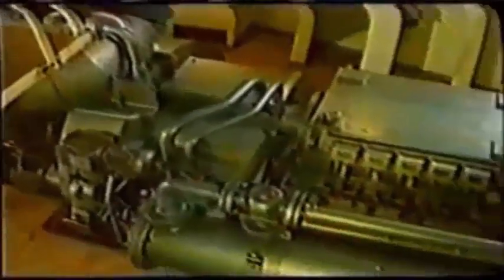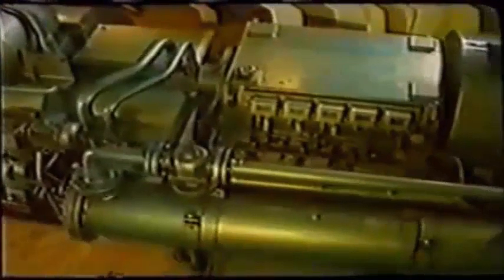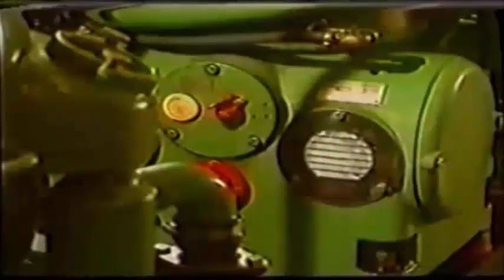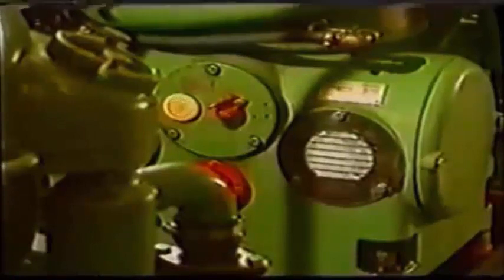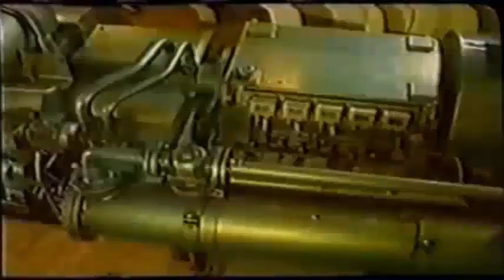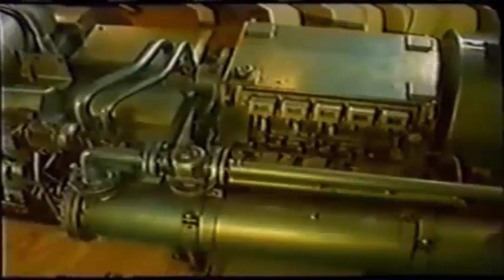There are a number of different types of gearboxes on board ship, ranging from the large gearing required for main propulsion by medium-speed engines, the open gears on the windlass, to the very heavily loaded gears on the purifier drives. Each requires a different lubricant. Main propulsion gears are not heavily loaded, and for this reason, in most cases, the main engine oil can be used in the gearbox.